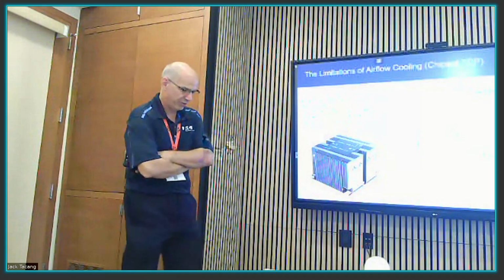So that diagram that I had, and let me move to this side here. This diagram over here is essentially a performance curve for a heatsink, an airflow heatsink, okay? What you're looking at here is the thermal resistance as a function of airflow as air passes through the heatsink. That thermal resistance will drop until it gets to a point where it flatlines. You can sort of see that portion down there, right? When it flatlines, it basically means that regardless of how much airflow I push through that heatsink, I am no longer effectively taking out any more heat from it, okay?